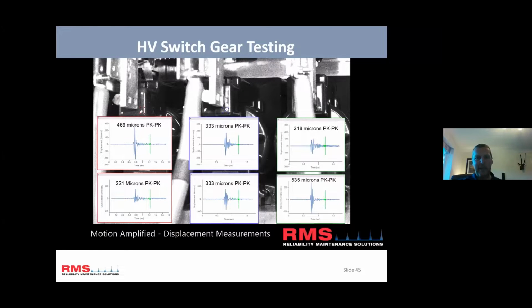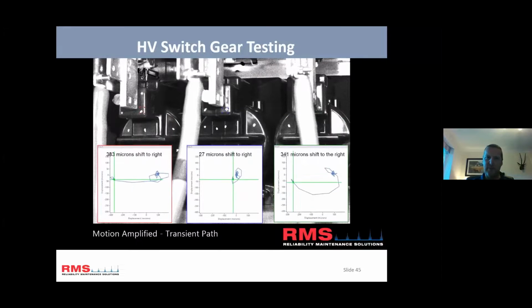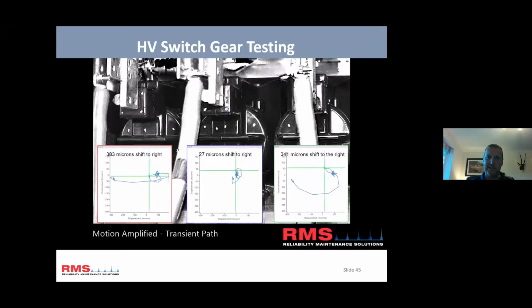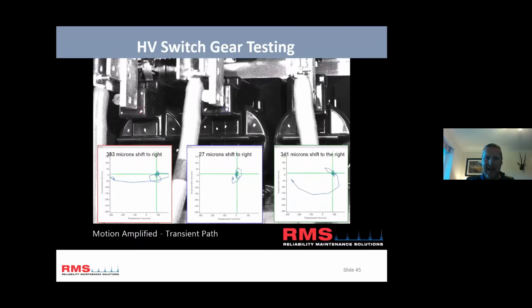What was happening, apparently, inside there were some cables that were rubbing, and when the insulation broke down, these things were exploding. What was interesting is when the arm comes down, we can see the whole body shift to the right, for distances of microns. So you can do some really amazing measurements with this technology when required. That data's gone to the customer, and they'll look at it with the OEM and decide a way forward.